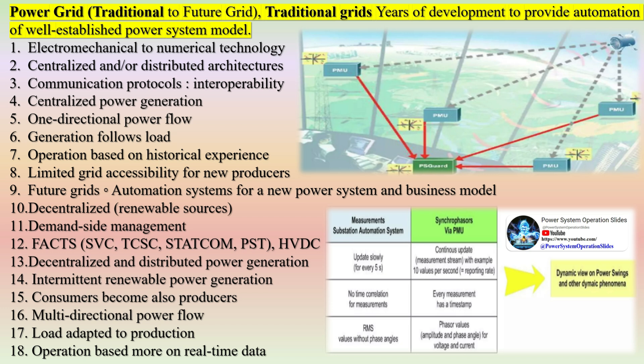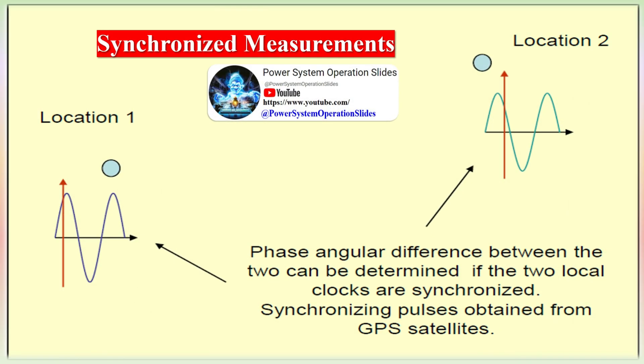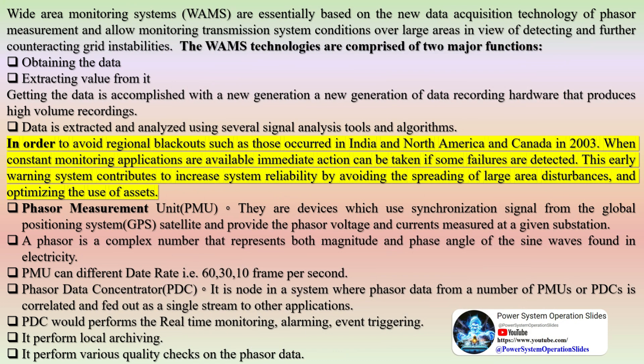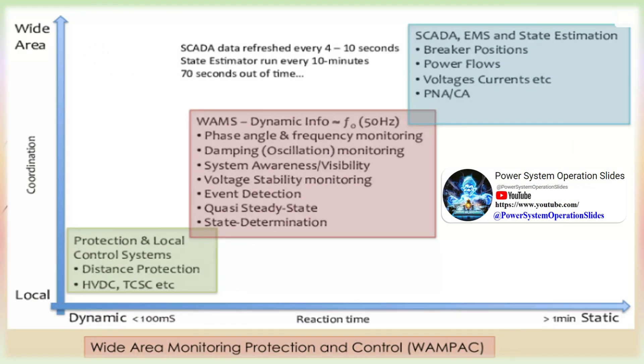The process of conceptualization, components, and architecture are required for the implementation of a WAMS data acquisition system for electric power systems. The issues found during the SCADA system operation are the low sampling rate, slow detection of errors, and inability to provide time synchronization signals. The typical SCADA system from 1965 to the present counts every electrical value every 10 seconds. This measurement is somehow bearable to monitor the power system in a stable condition; however, during uncertainty and disturbance in the electrical network, this measurement level is not good enough to monitor the varying effects in the system.